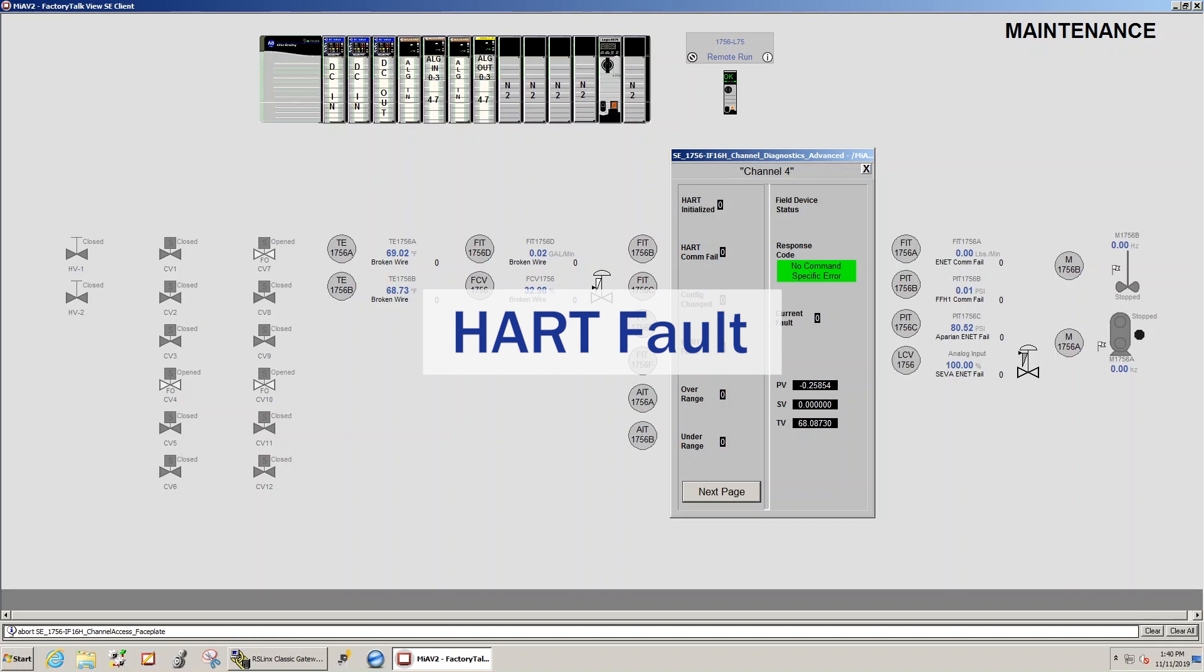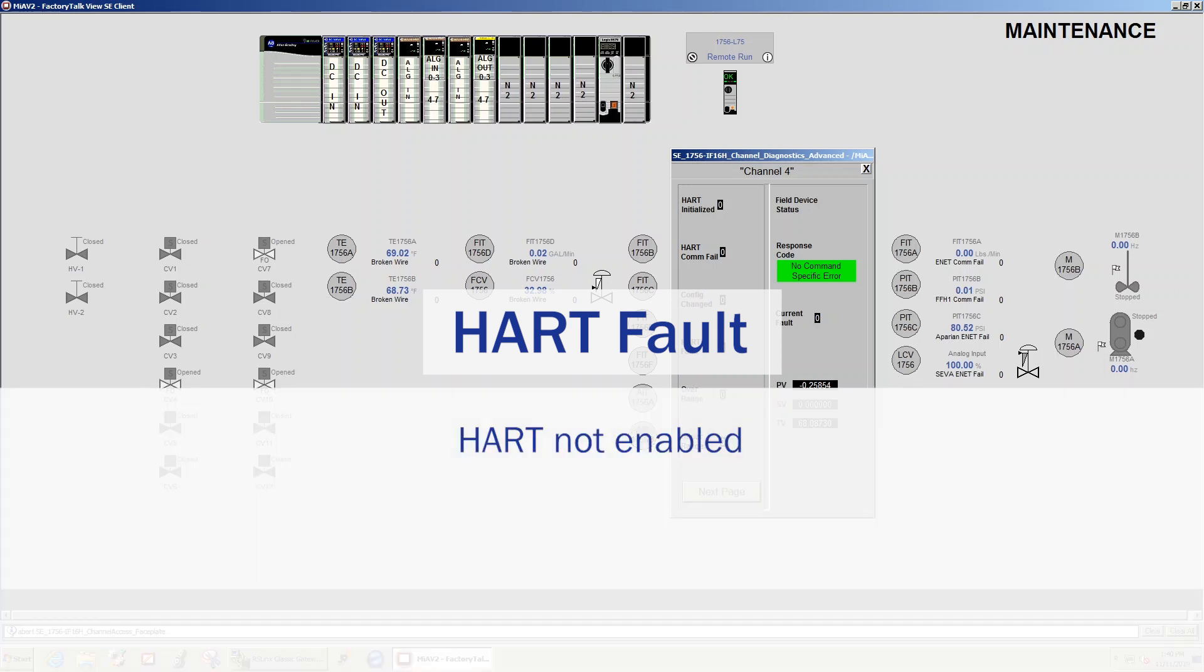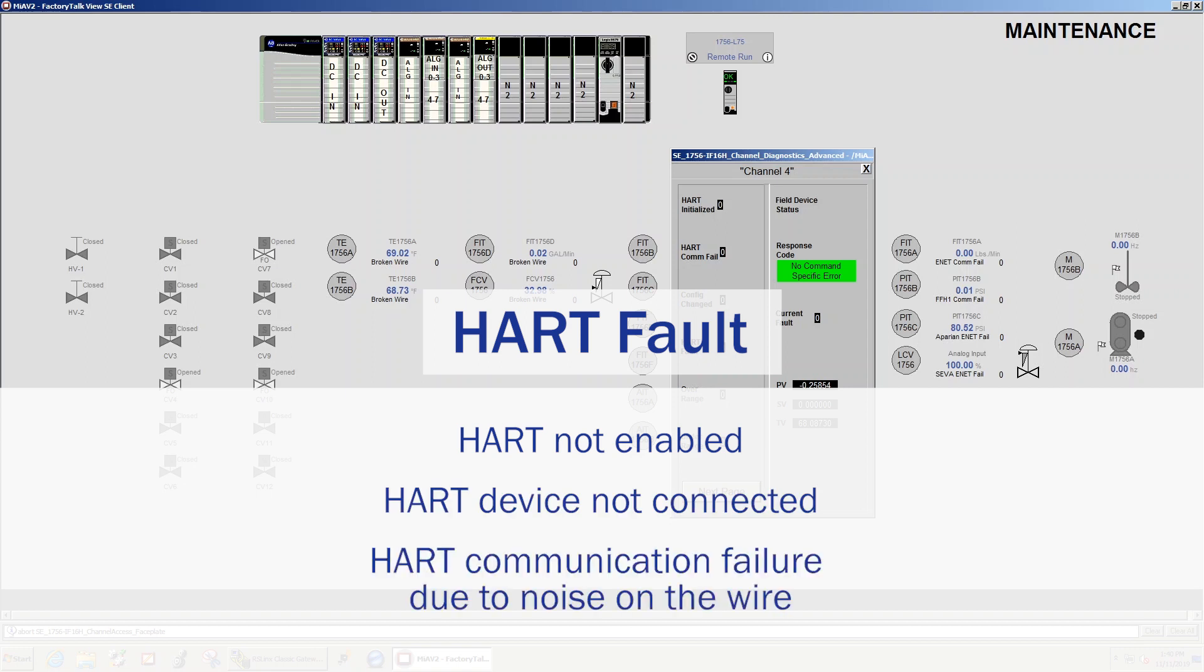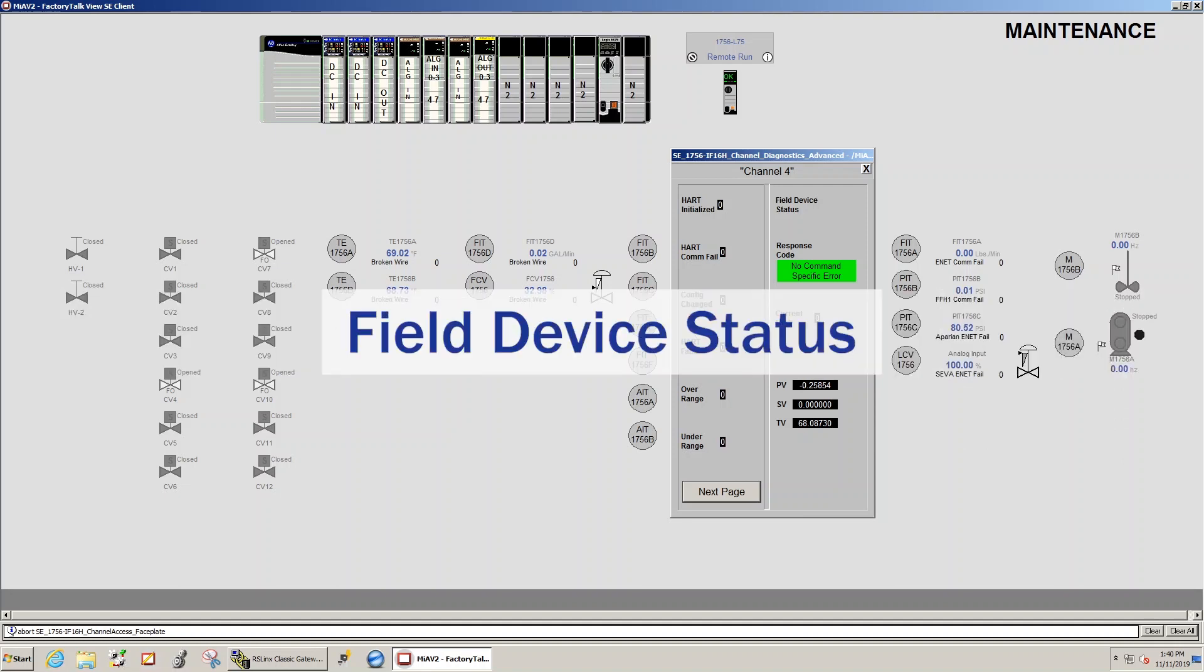Some examples of this are HART not enabled, HART device not connected, or HART communication failure due to noise on the wire. Field device status, HART device status byte from a recent HART reply indicates the health of the HART field device.